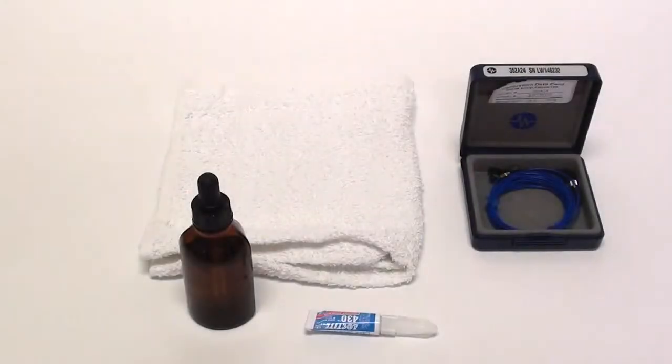Miniature or teardrop accelerometers are a common choice when weight of the transducer must be kept to a minimum. Mounting and removal of these sensors require special care to avoid damaging the delicate lightweight construction.